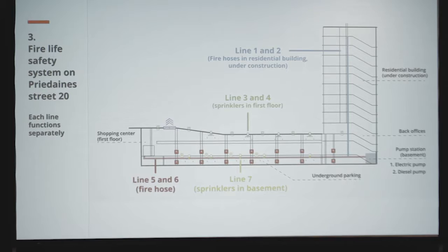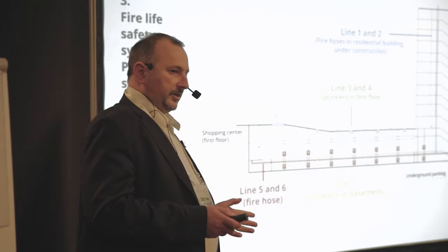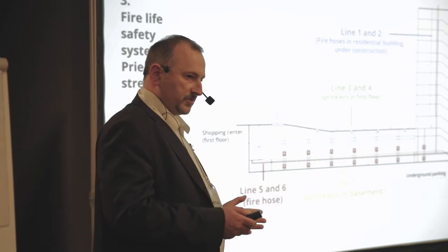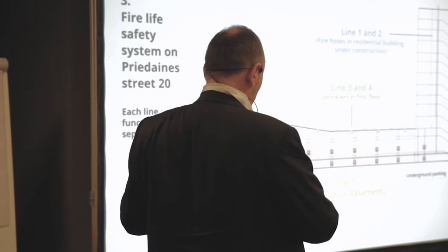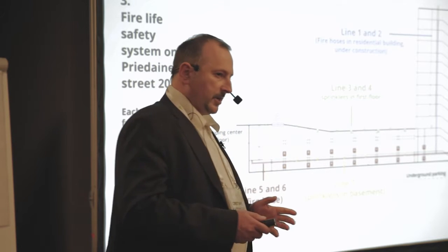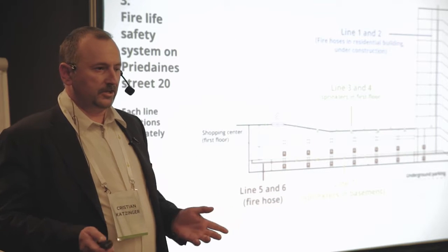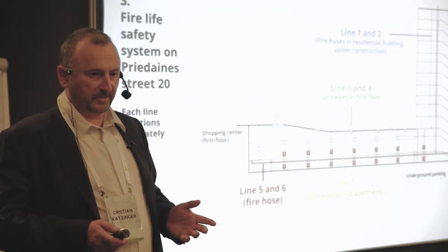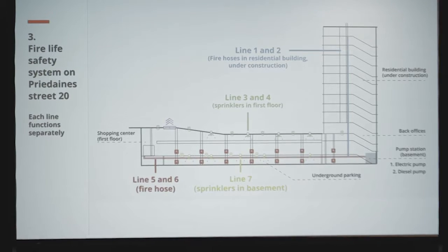That's how the firefighting system is designed in Priedaines Str 20. We've got here on the left side the pump station in the basement, from where the supplying of all systems came from, with an electric pump, and in case there would be a problem with the electricity power, there's a second supply, a diesel pump.